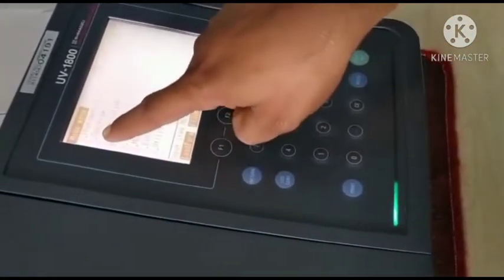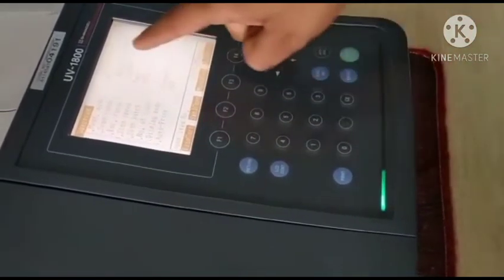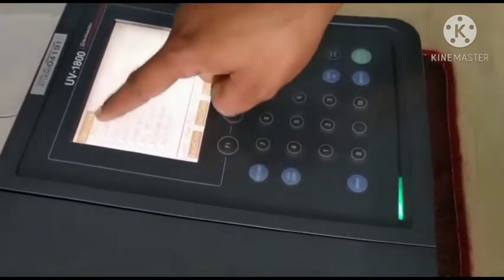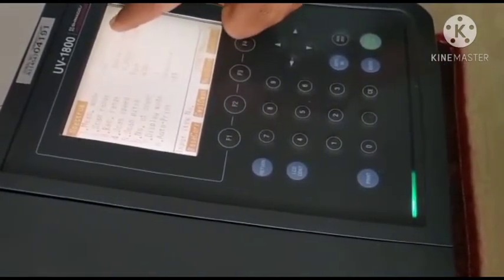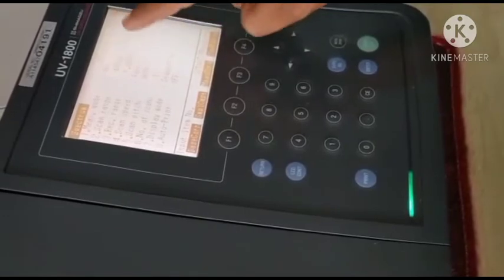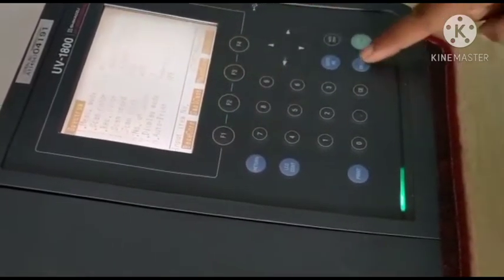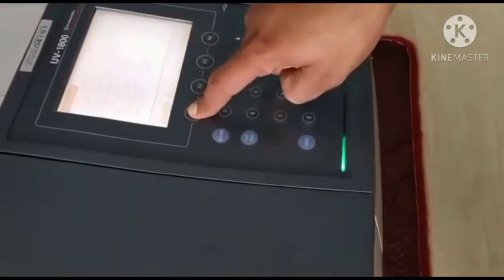Now after closing the box, we have to go to spectrum mode. Since spectrum mode is in 2 point, so I will select that, and here are the details of spectrum mode. This is the calibration range. This is absorbance mode. This is from 200 to 400 nanometer, and I will start the scan. First I will give the baseline correction. In baseline correction, the range between all UV wavelengths, that is 200 to 400, is auto zeroed by the water. That is, water will not show absorbance anymore now.